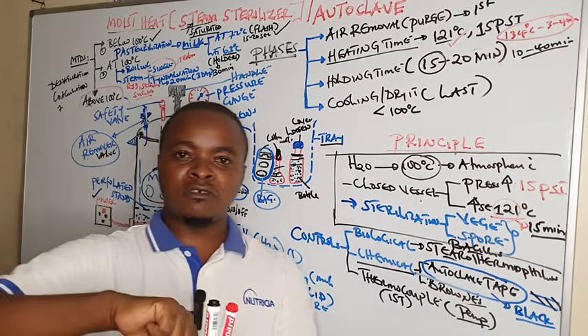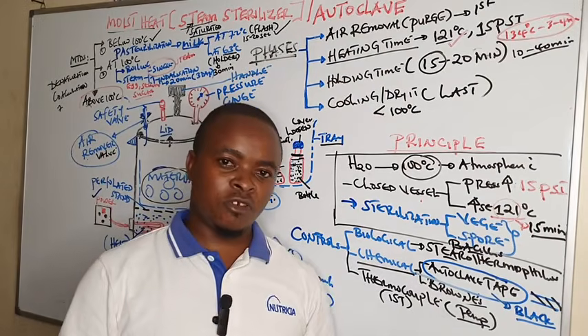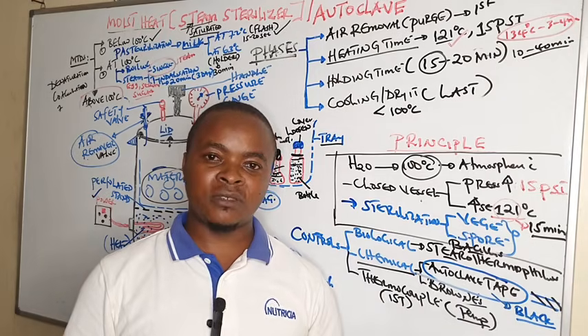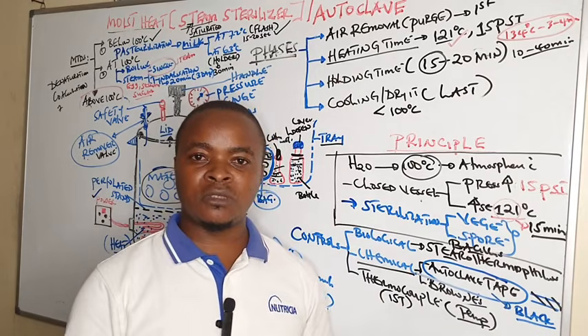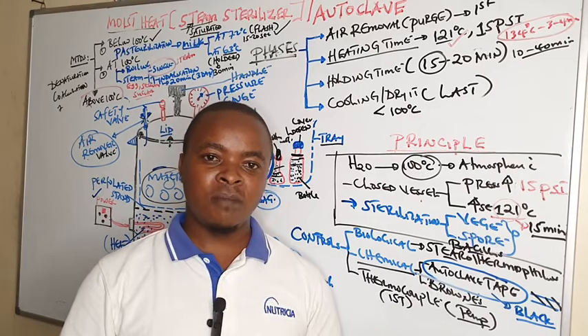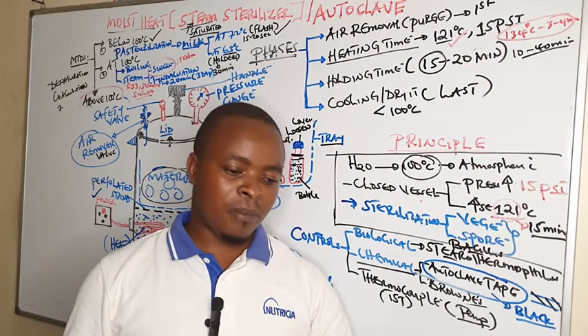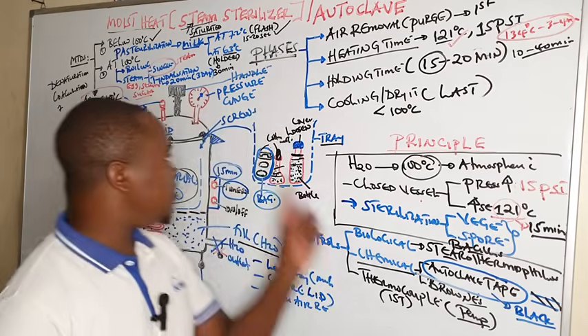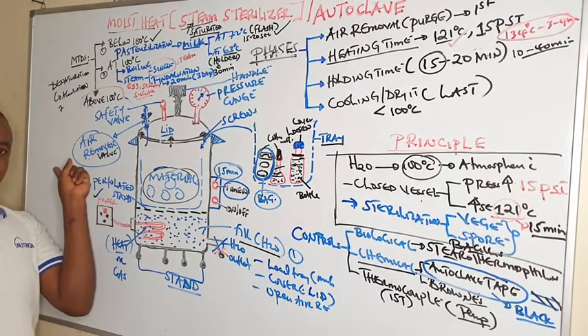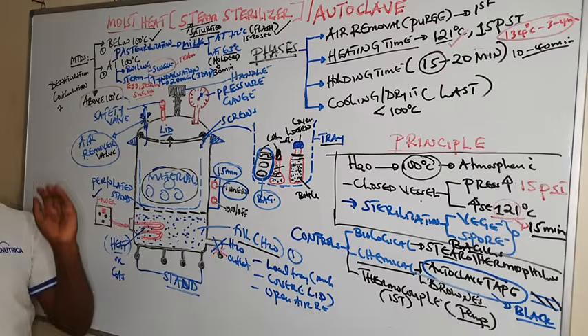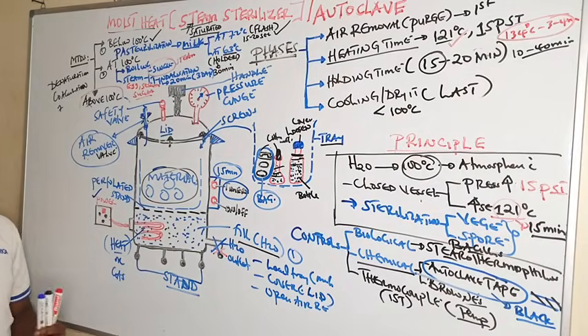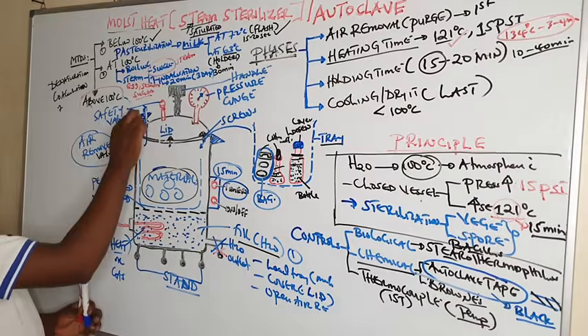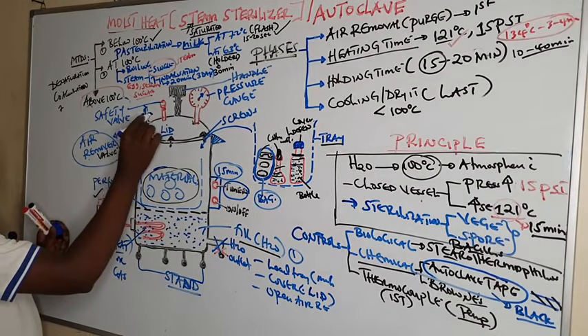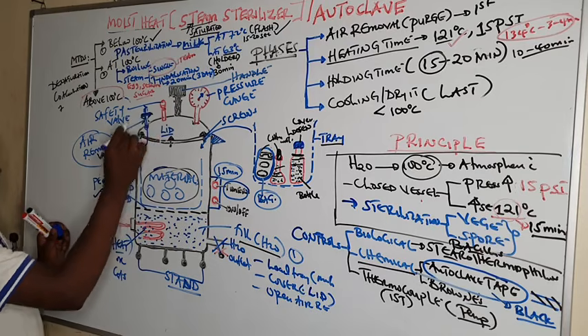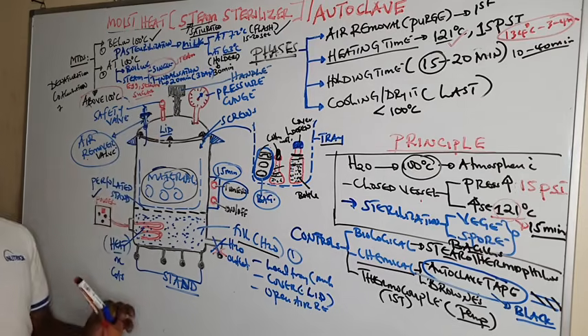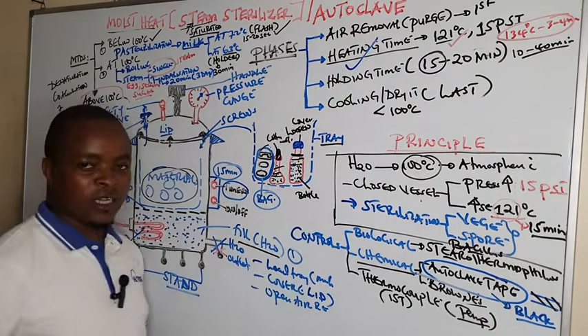You can connect a tube and put it in water to see if there are air bubbles. If there are still air bubbles coming out, it means the air is still present. But if we see no more bubbling when we connect the tube from the valve to the water, it means all the air has been removed. And when we ensure that all air has been removed, we come and close the air remover again. We close, and after closing, our autoclave will begin heating up.